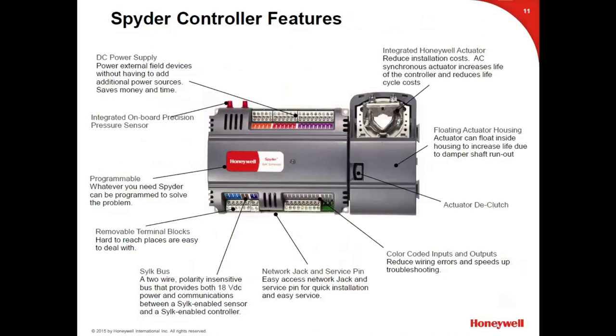Particular models include a pressure sensor built in. In the lower left corner there's the Sylk bus — a Honeywell proprietary two-wire polarity-insensitive bus that provides both power and communication between our controller and Sylk devices. We have space sensors, actuators, and outside air and return air type sensors on the Sylk bus. It saves I/O and eliminates wiring mistakes because it's just a two-wire bus. You can daisy chain it — and because it's polarity insensitive, it's very difficult to make a mistake when wiring.